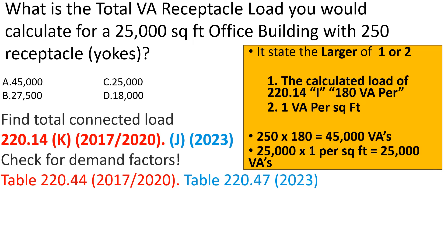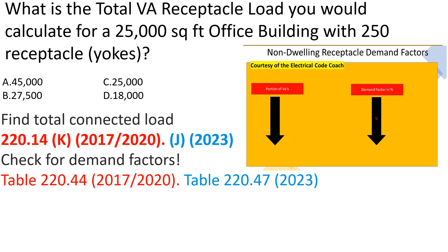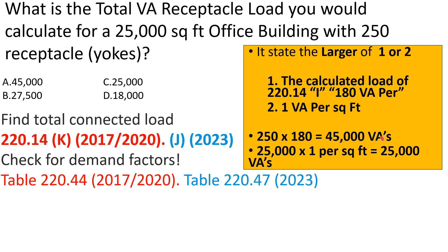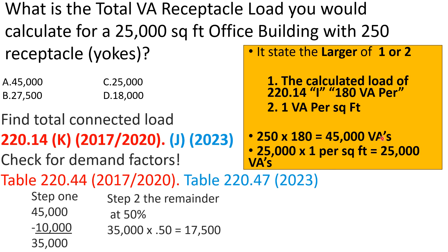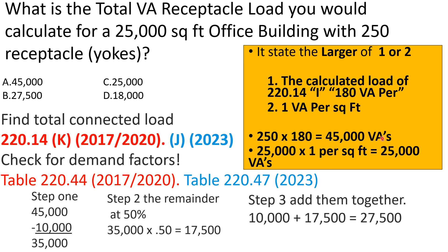That leads us to Table 220.44 if we're in the '17 or '20, or Table 220.47 if we're in the '23 — same information, different title. This table for non-dwelling unit receptacles works similarly to Table 220.42/220.45: the left side gives our portion of VAs and the right side gives our demand factor percentage. We take the first 10,000 VAs at 100%, then take the remainder and multiply by 50%. We take the 10,000 we set aside, add it to the new reduced load, and we get 27,500 VAs. We select B. Great job.